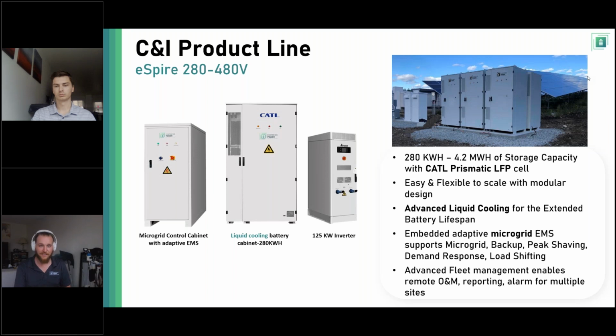One thing to note is that this energy storage system is liquid cooled. Versus an HVAC air conditioning unit blowing on the battery cells, it uses an integrated liquid cooling system, so there are no external water lines, just ethylene glycol to remove heat from the cells. It's essentially a heat exchanger unit.